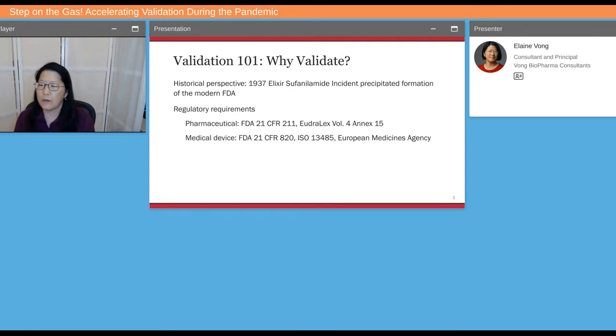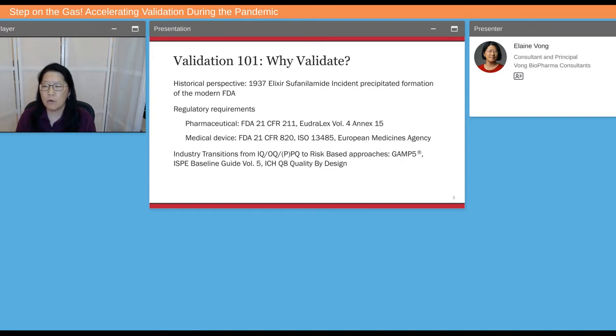And also ISO 13485. So over the last 20 to 25 years, we've seen a movement from just installation qualification, operational qualification, process qualification to risk-based approaches for leveraging factory acceptance testing, site acceptance testing, and design qualification, and then executing reduced IQ, OQ, PQ, or PPQ testing once on site. Some of these risk-based approaches involve GAMP 5, which is for GxP software systems, ISPE Baseline Guide 5, and the International Council for Harmonisation Q8 Quality by Design. We're able to leverage these things in order to take a risk-based approach to validation activities. See the slide participant packet for more regulatory information, industry guidance documents, and more.